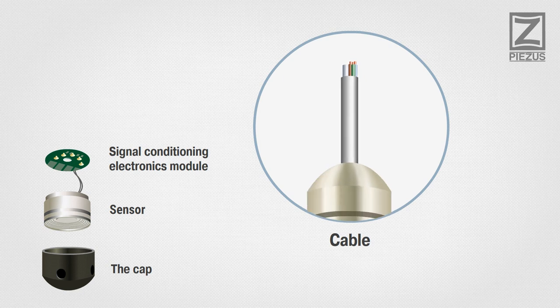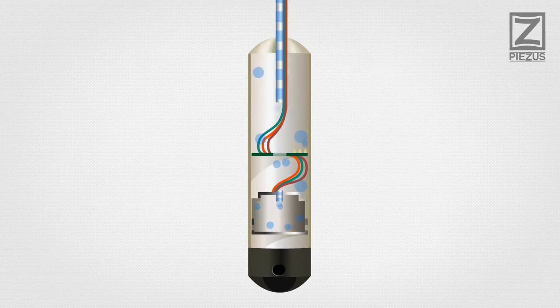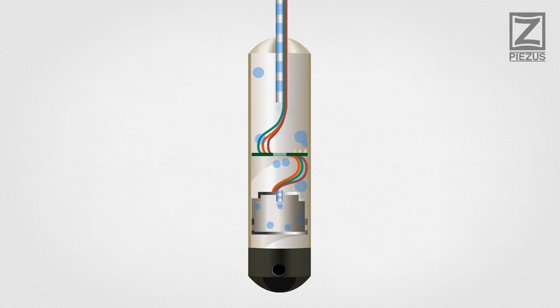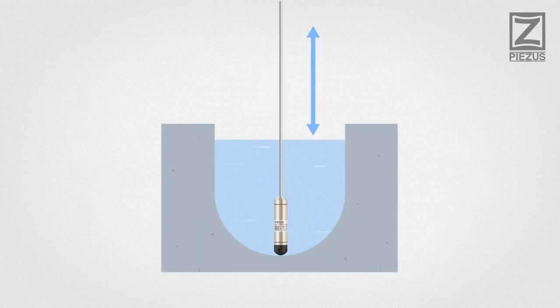The capillary tube delivers atmospheric pressure to the backside of the sensor element's diaphragm to compensate for possible fluctuations in the atmospheric pressure.